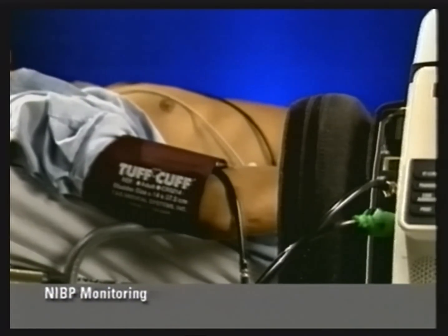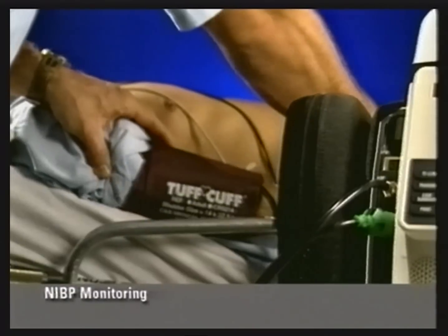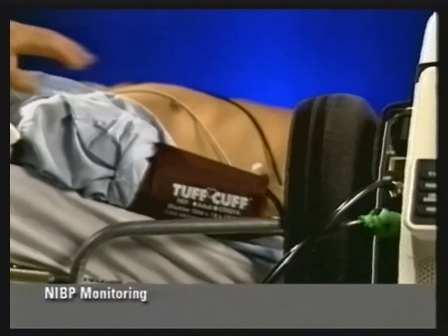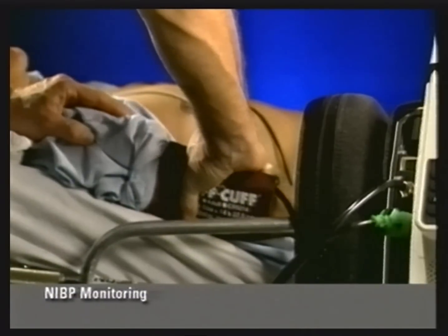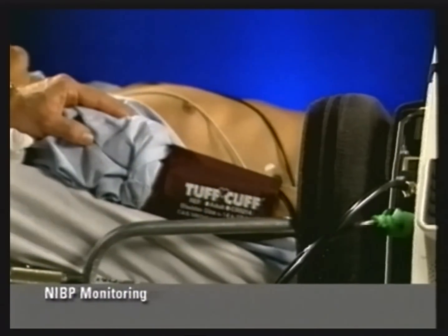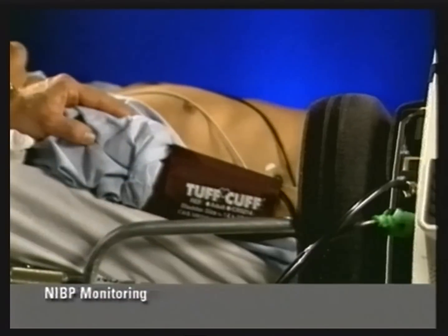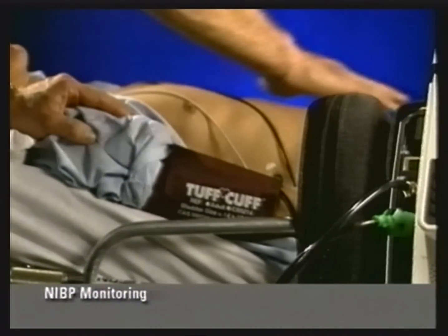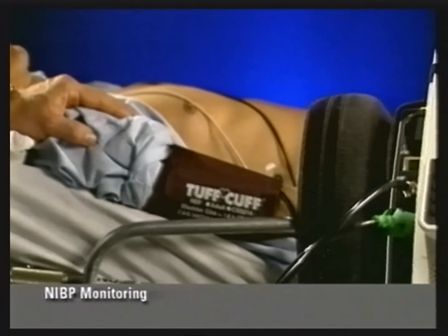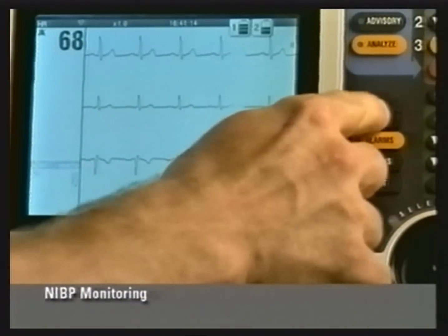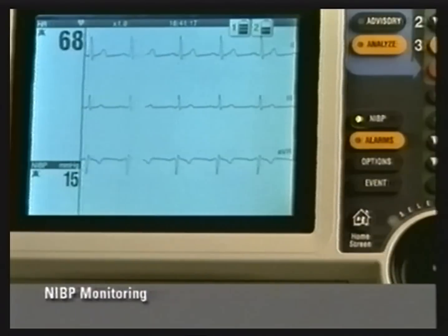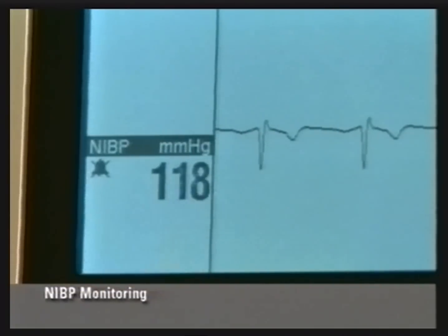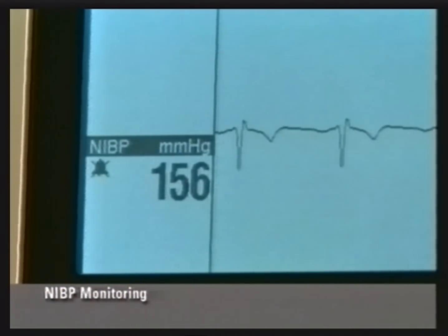Position the patient's arm in a relaxed and supported position at about the same level as the patient's heart. Tell the patient that the cuff will inflate and cause a big squeeze around the arm and that his or her fingers may tingle. Advise the patient not to move their arm during the measurement because it could make it even more uncomfortable. Press NIBP to start a measurement. The NIBP area shows the increase in pressure as the cuff is inflating. When the inflation pressure is reached, the cuff slowly deflates and the blood pressure measurement is obtained.